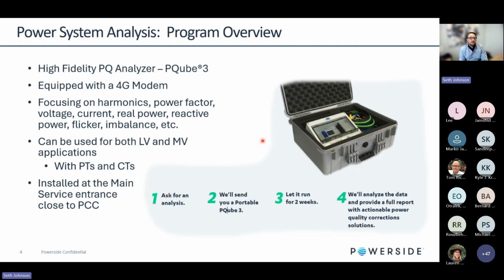The idea of this program is that it's really designed to look at a full power system, not necessarily an individual panel or an individual load. Now, there are some exceptions to that rule. For instance, if a client has a rectifier that's producing a lot of harmonics upstream, okay, maybe we want to look directly at that load individually. But this program is not designed to do a load study to determine if you can add more load to your system. It's very much focused on power quality, which is why we're using such a high fidelity Class A power quality analyzer. There's certainly other products out on the market if you're just trying to do a basic load study.